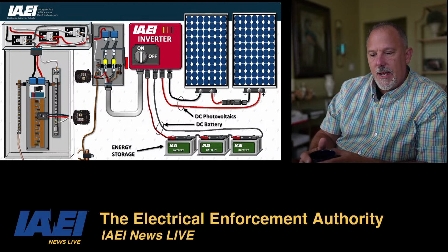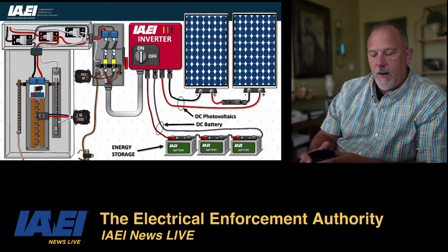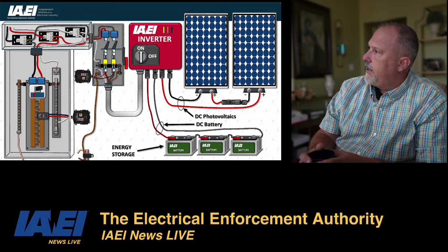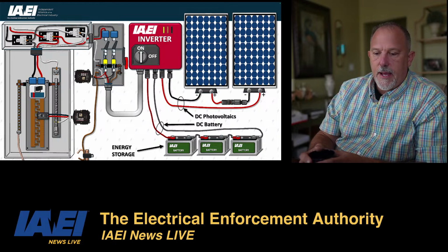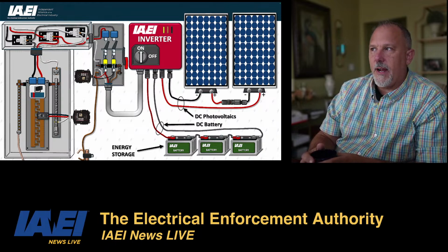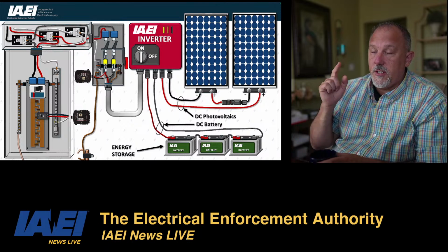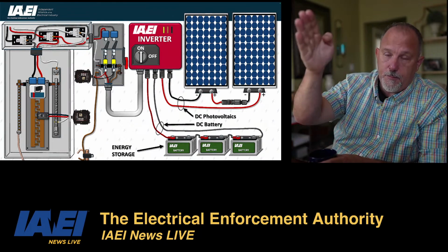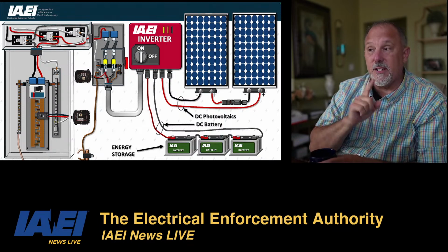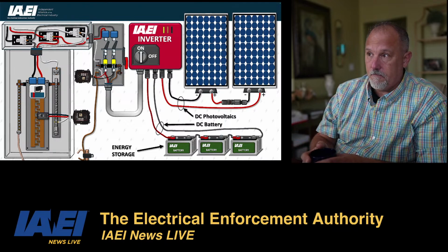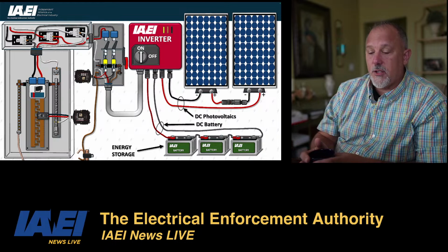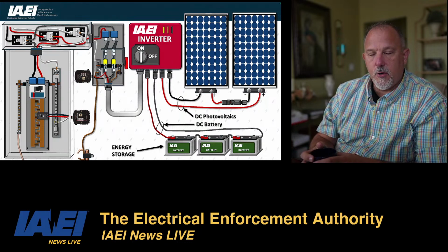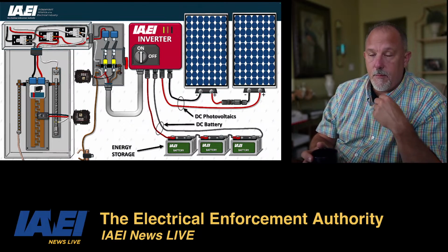Robert Nelson in the house. How would adding a few solar panels affect the service coming off of the pole? My thoughts on that, Robert, you're probably going to pull less current when you are providing power from the inverter. You may have restrictions because you may be putting power up to the pole, but make sure you talk to your utility because some utilities don't permit that. They need to know about that. I'm not sure, Robert, if I'm answering your question correctly, but those are my immediate thoughts.